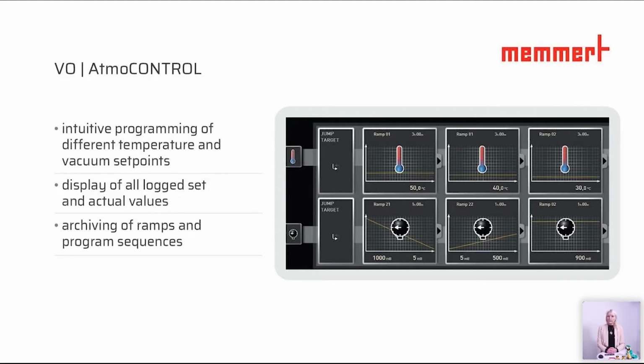And that is possible when you use our AtmoCONTROL software, which comes along with the vacuum oven and is included in the standard delivery display. So it's very, very easy to set a profile, and you do this different setting of temperature values and pressure values. This is, for example, requested. You know, a drying of powder is not so easy, but if you have a large amount of powder, how can you dry it?